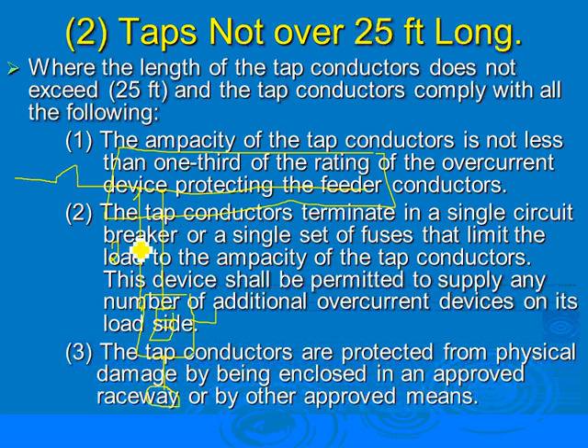So that's condition number one. You can't be over 25 feet. And like we said, probably end up with 24 anyway between enclosure to enclosure. Okay, what's the rule? Let's tap a 600 amp. Make it easier. Here's my 600 amp. Or you know what? Because we already tapped a 400, let's just continue with the 400. Let's tap at 400. So the code says, guys, the conductors here cannot be less than 1/3. So what's 1/3 of 400? 1/3 of 400 is what?